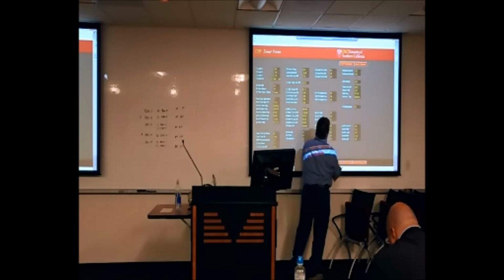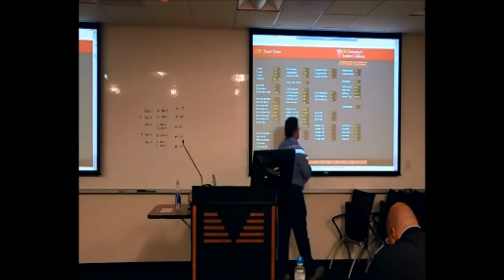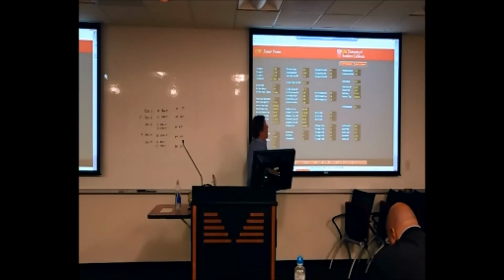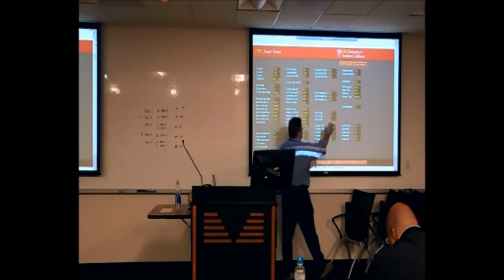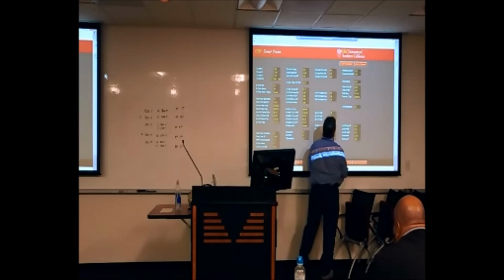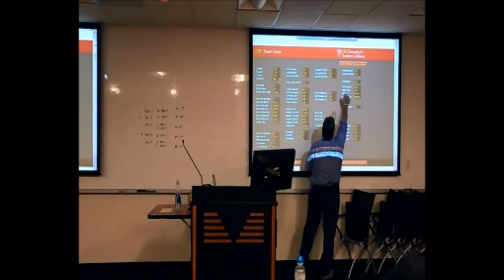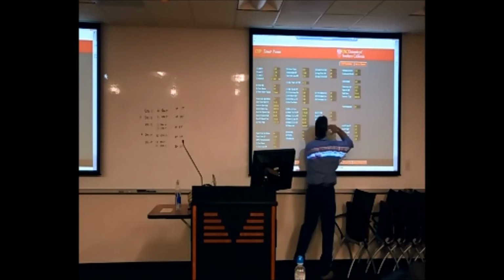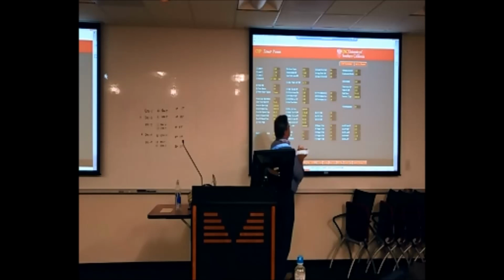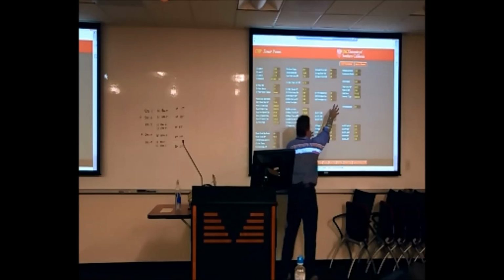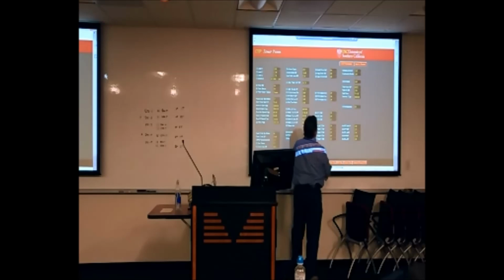Cooling tower alarm suppressed. That means when we first bring the tower online, we're going to suppress all the alarms for maybe 15 or 20 minutes so we don't have false alarms. So the suppression is off right now, meaning all the alarms can roll through. We have a ton-hour calculation over here that was existing from before. This is the overall ton-hour for the CHP central plant. It was displayed on this screen, so likewise it's being displayed again.